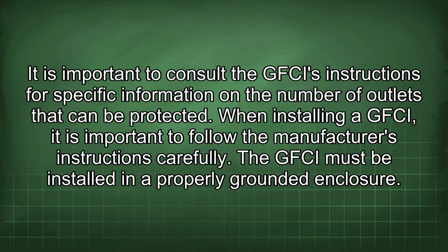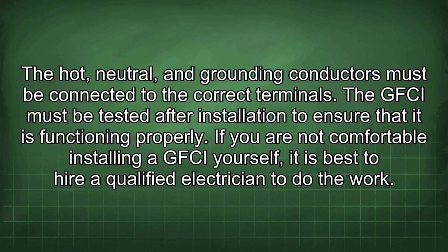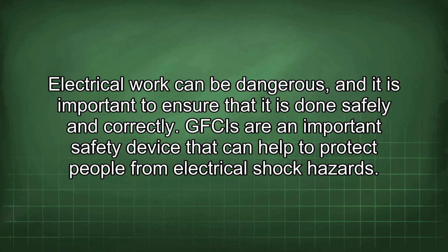The GFCI must be installed in a properly grounded enclosure. The hot, neutral, and grounding conductors must be connected to the correct terminals. The GFCI must be tested after installation to ensure that it is functioning properly. If you are not comfortable installing a GFCI yourself, it is best to hire a qualified electrician to do the work. Electrical work can be dangerous, and it is important to ensure that it is done safely and correctly.